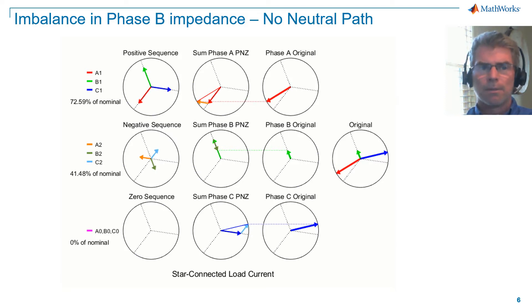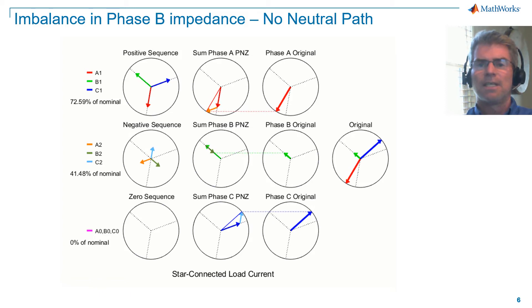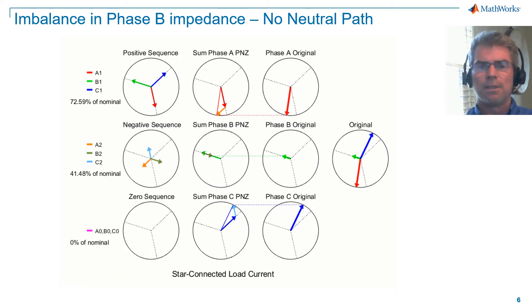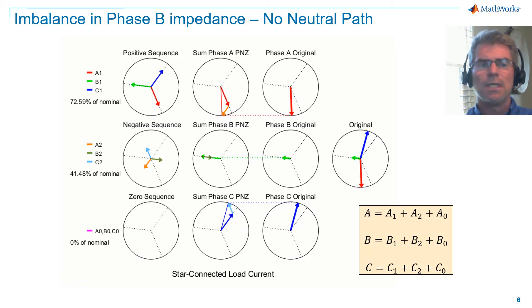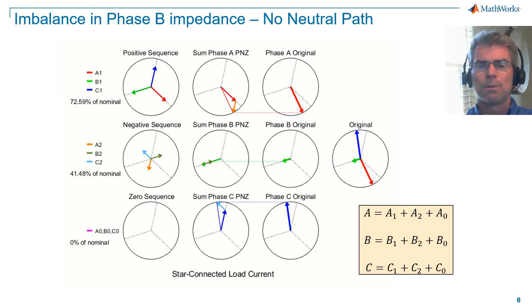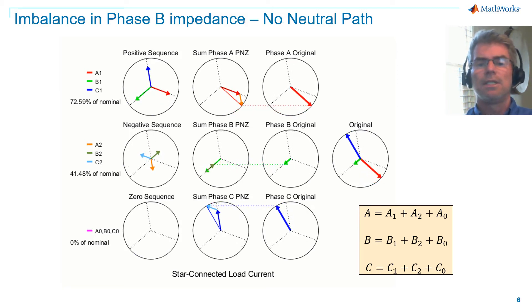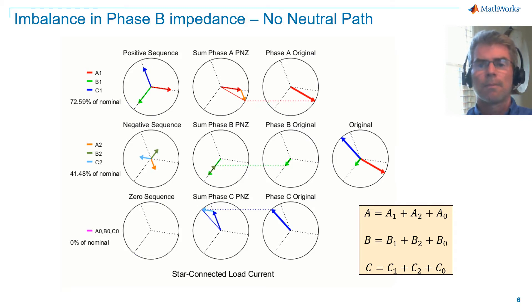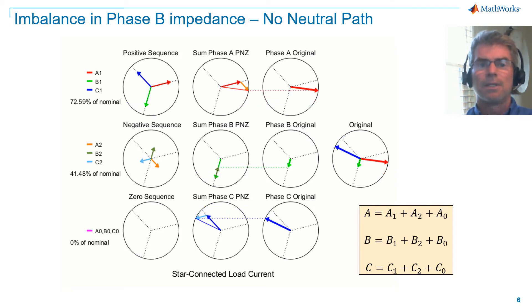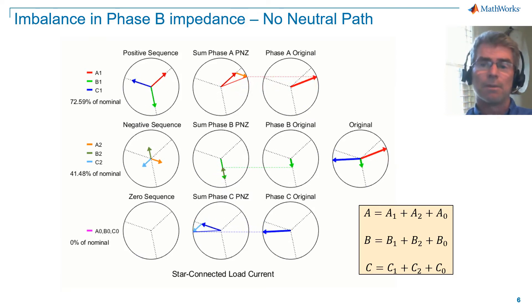In the middle column, we add the sequence vectors to reconstruct the original vectors. For phase A reconstruction, we add A1, A2, and A0. For phase B reconstruction, we add B1, B2, and B0. For phase C reconstruction, we add C1, C2, and C0. Note that we have a measure of how unbalanced the system is, with the negative sequence being approximately 41.5 percent of nominal for this example.